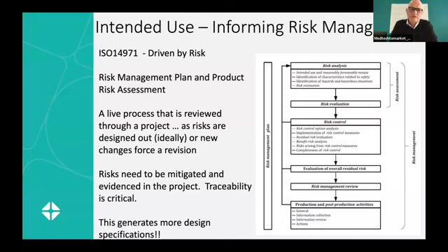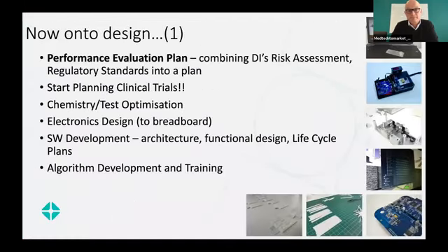And you list all of those risks that you can foresee of it being misused, misdiagnosed, all that sort of stuff. And that document is a live document, but it actually might generate more design specifications, because you need to demonstrate during the course of a project, and this is a cyclic thing, that you actually need to revisit and show that you're designing out the risks, and then you have whatever residual risks. And again, with the FDA, you will be submitting a risk management plan and your risk assessment, and you will be listing out any residual risks that are left within the project.